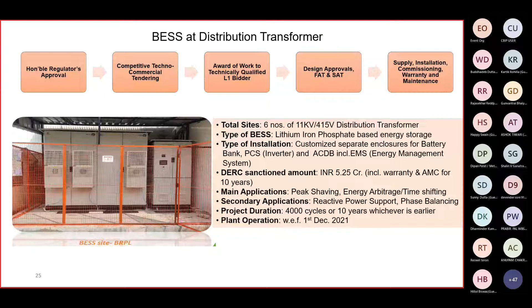For sizing the battery energy storage, we identified overloaded distribution transformers that were also space constrained, where we were not able to upgrade or augment to the next higher capacity. Then we estimated the continuous overloaded instances and peak loadings beyond a predefined threshold, say 70% or 80%, and sized the kilowatt and kilowatt-hour required for each site.